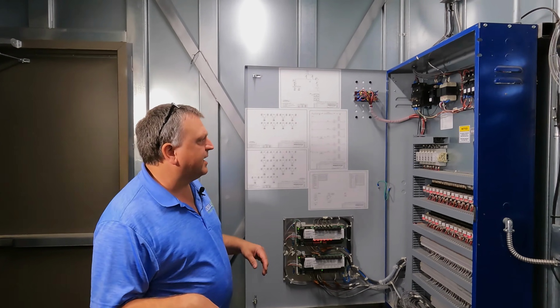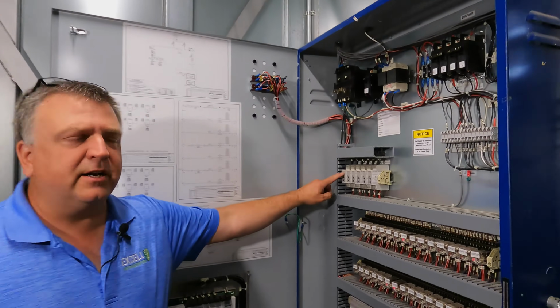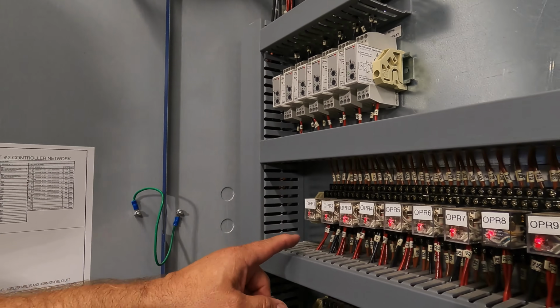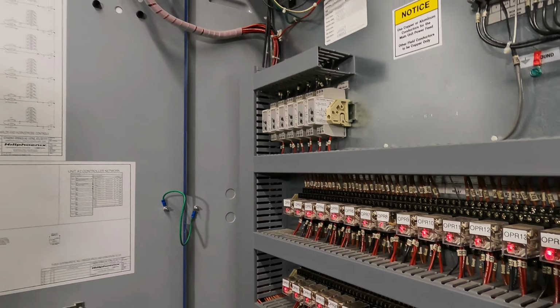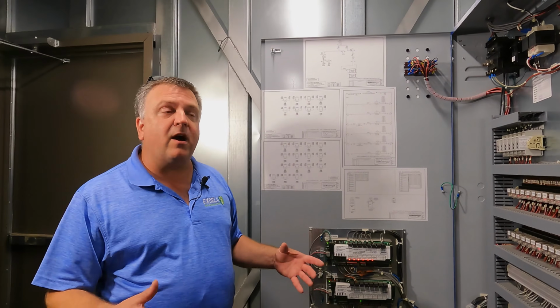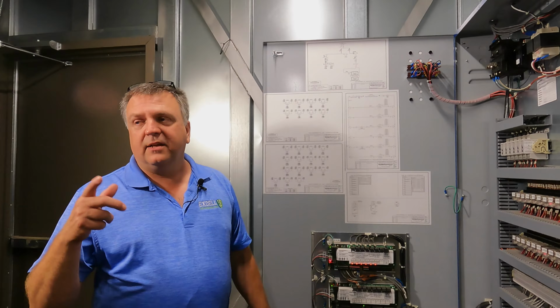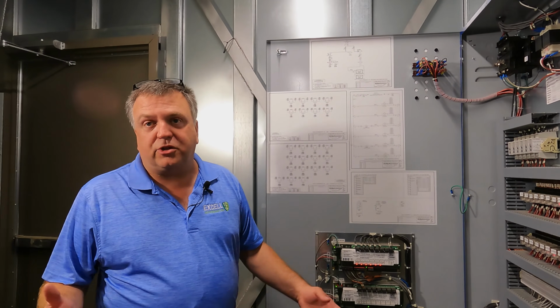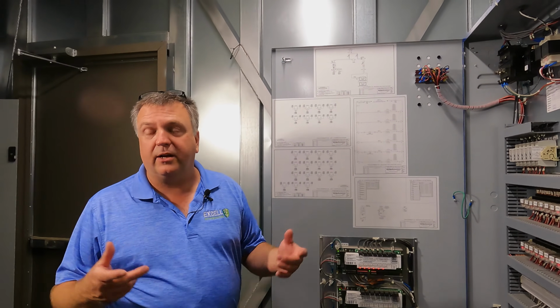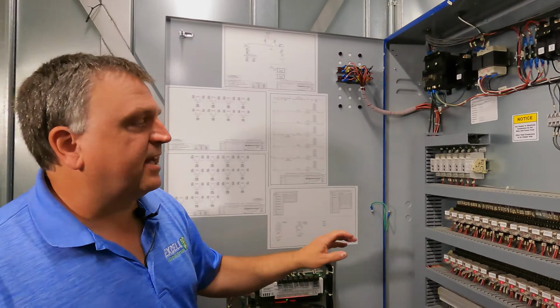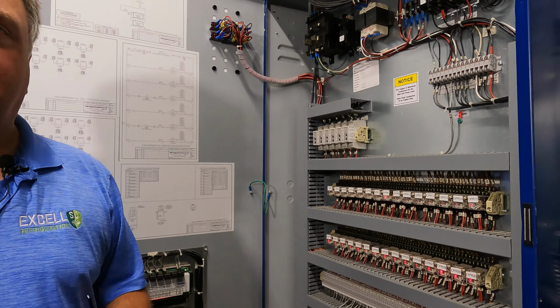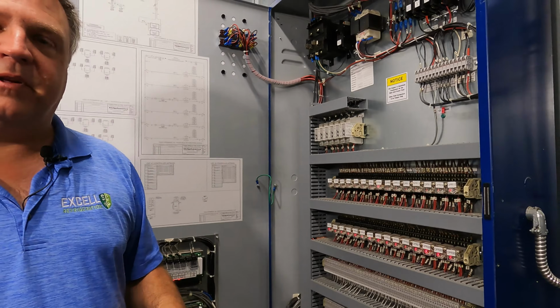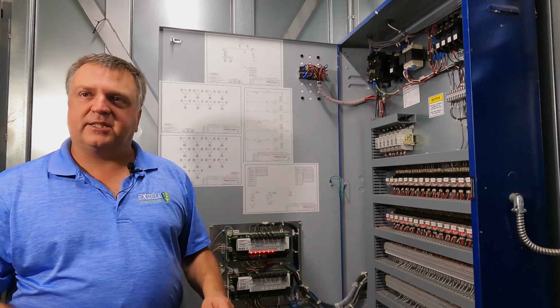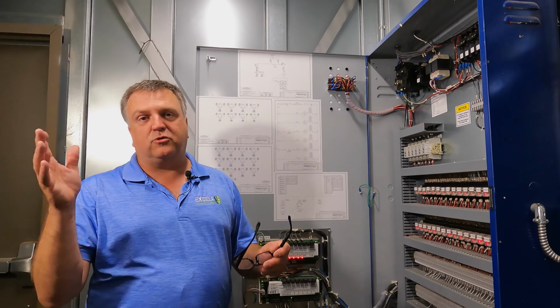After that 15 minutes, our first timer is going to energize. This is going to bring on our first set of relays because we don't want to bring them all on at once. If I try to bring all that heat back up here at once, those compressors aren't going to be able to handle it. It's going to shut off on a high pressure. We're going to hit over 500 pounds. Time delays are set up 15 minutes apart. We're starting to cool some of the cases down, bring some heat up. Our pressures are rising, and then they're dropping again.